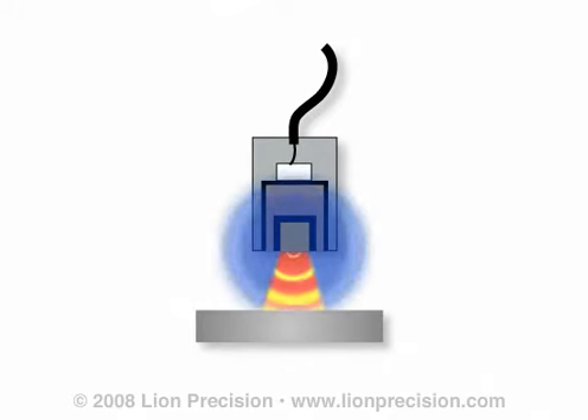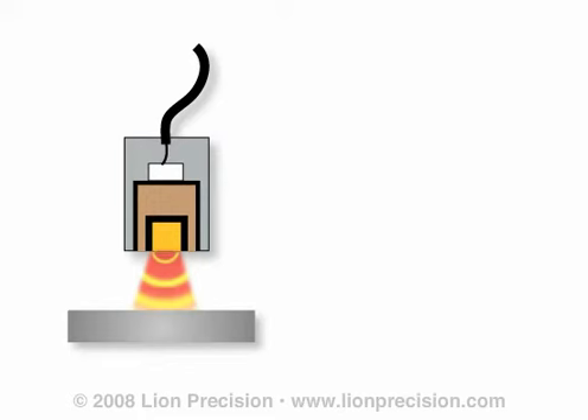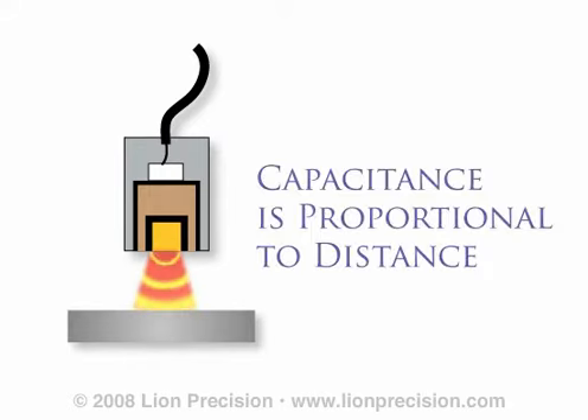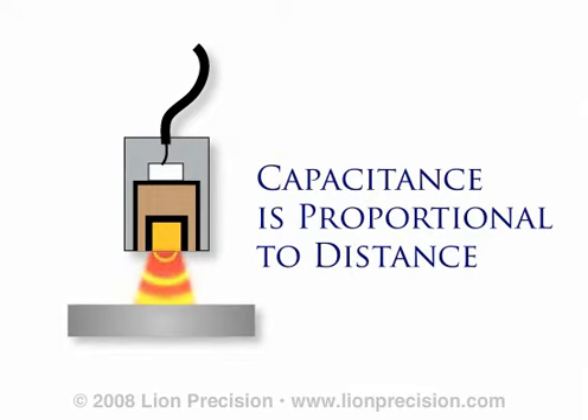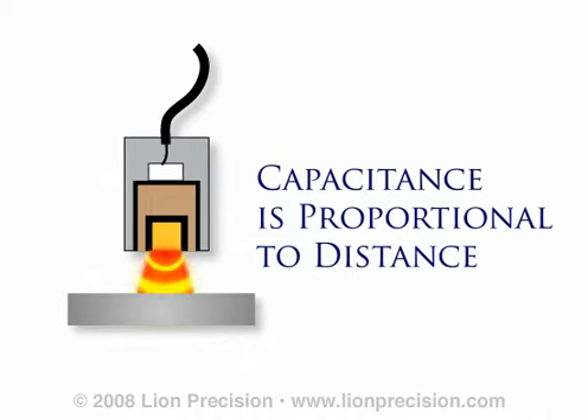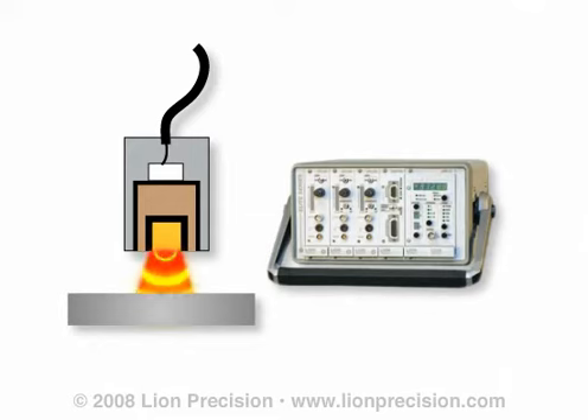The amount of current flow in the electric field is determined in part by the capacitance between the sensing element and the target surface. Because the target and sensing element sizes are constant, the capacitance is determined by the distance between the probe and the target, assuming the material in the gap does not change. Changes in the distance between the probe and the target change the capacitance, which in turn changes the current flow in the sensing element. The sensor electronics produce a calibrated output voltage which is proportional to the magnitude of this current flow, resulting in an indication of the target position.